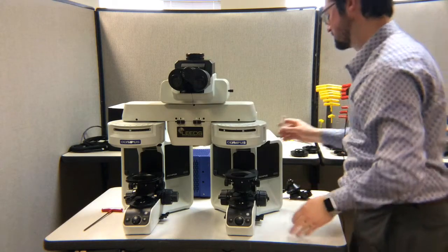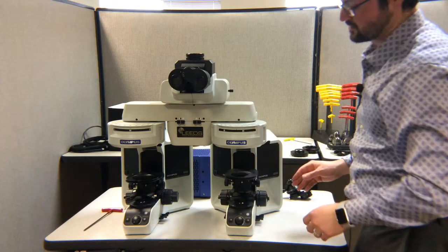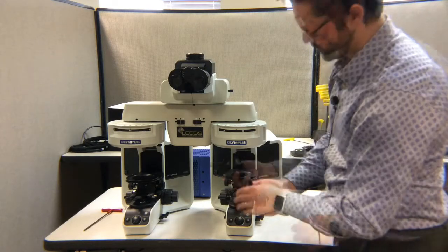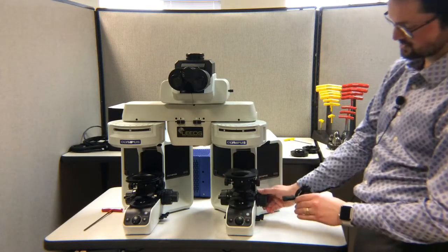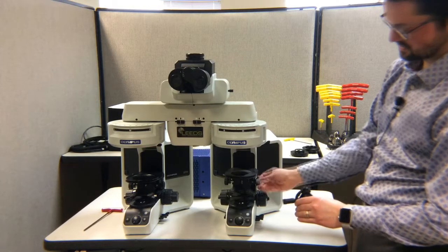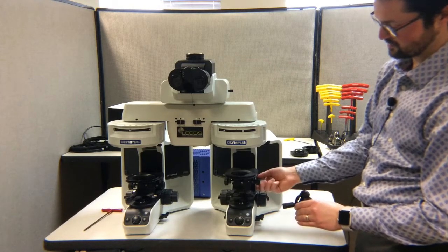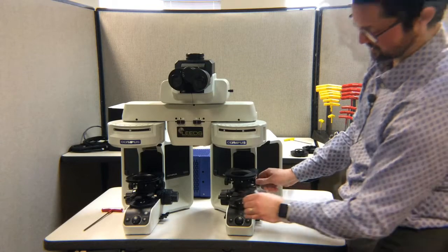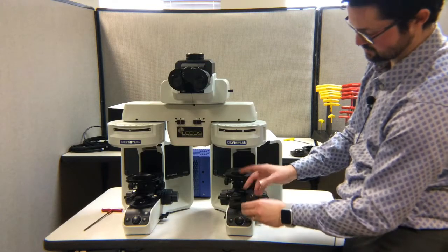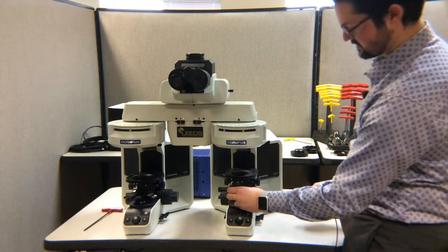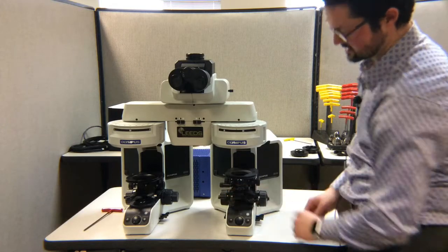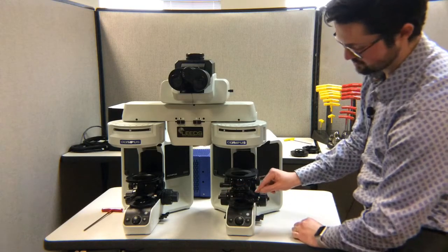Okay, so our next step is going to be to mount up the condenser and then the stages. This is our polarizing light condenser. We're going to go ahead and mount it here. First thing I'm going to do is bring the focus up of the stage using this focus control, and I'm going to bring the condenser down a bit and then flip the flip top so it doesn't bump into the top of the stage. And then this whole thing slides in, and then there's a little locking screw on the right.